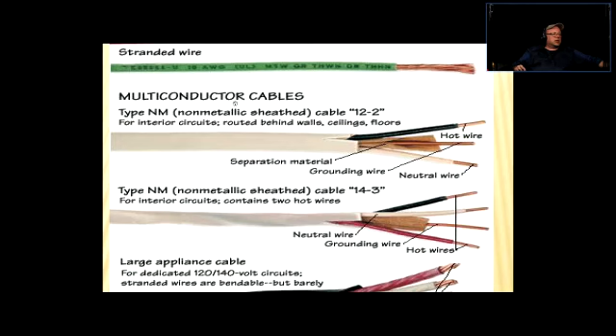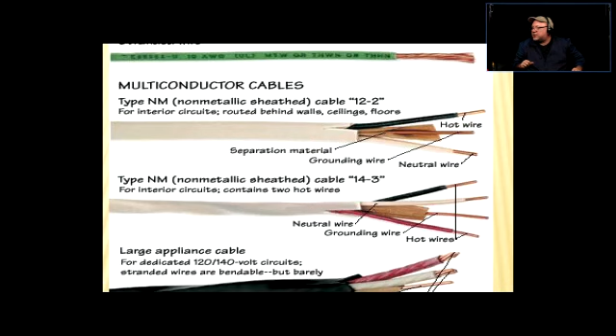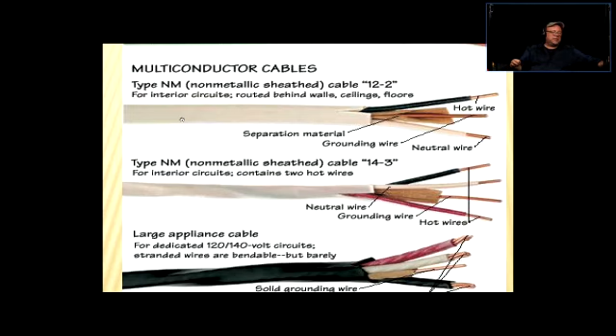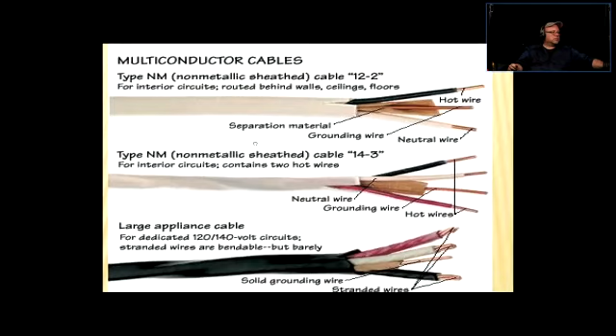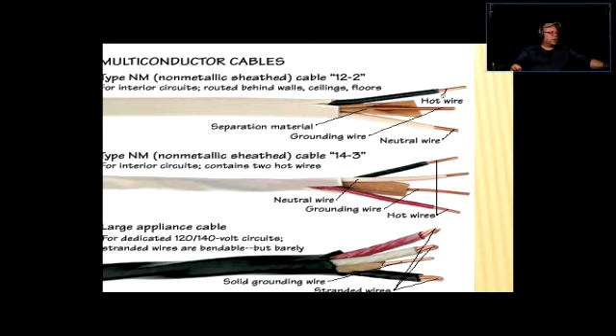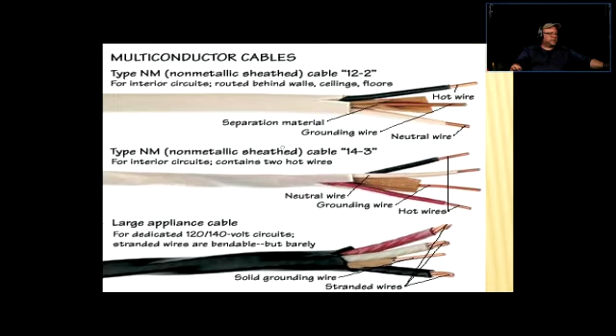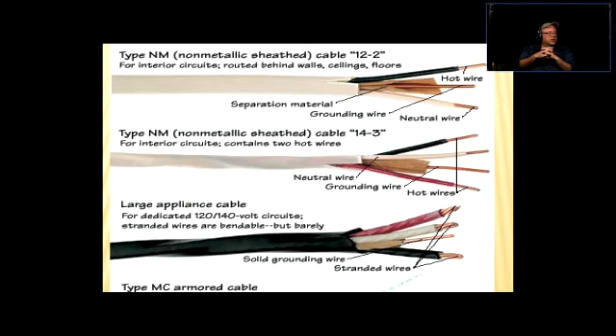Here's another thing that's going on here. Multi-conductor cables. Type NM stands for non-metallic sheathed cable. 12-2. Well, the gauge of that is 12, and it has two current carrying conductors. That's basically what that says. Non-metallic, well, it's a PVC jacketing. So what do we have here? We have the neutral wire, which is always white. The neutral is always white. And then the other colors are going to be mostly hot, unless they're not. Right? So here's the hot wire, that's the black one. And here is the grounding wire or bonding wire. And we all know what the difference between grounding and bonding is now. If not, rewind. Okay. All right.